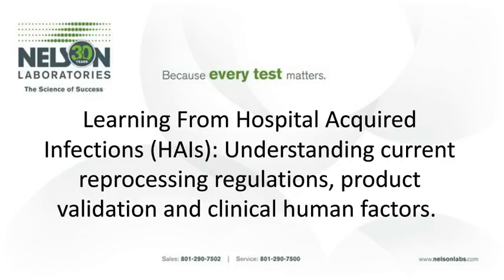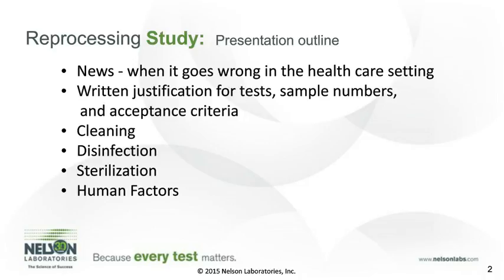First, we will be talking about some news articles that have just recently come into the news of when it goes wrong in healthcare settings. We will then get into written justifications for tests, sample numbers, and acceptance criteria. Next, we will be discussing validations of cleaning, disinfection, and sterilization of reusable medical devices. And then we will touch on human factors associated with this type of testing and the reprocessing of medical devices.